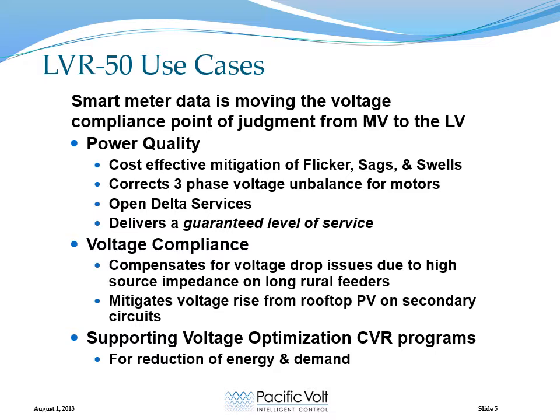So the regulator will compensate for voltage rise due to reverse power flow on the secondary circuits. It also compensates for voltage drop due to high source impedance on long rural feeders. And it can be selectively applied in CVR programs to maintain compliance for outliers which have too low a voltage. This allows you to lower the medium voltage feeder voltage more than you would otherwise be able to.